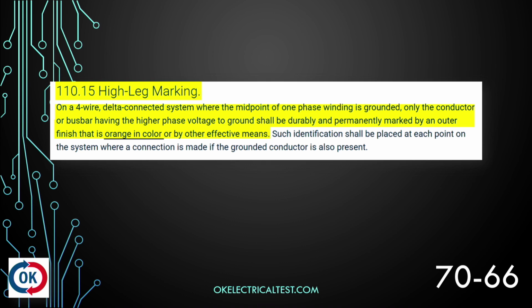110.15 high leg marking. It says on a 4-wire delta-connected system where the midpoint of one phase winding is grounded, only the conductor or bus bar having the higher phase voltage to ground shall be permanently and durably marked with an outer finish that's orange in color or by other effective means. So the high leg on a 4-wire delta-connected system can be marked, indicating with color the high leg, and that would be orange in color. All right, or it says we can also use other effective means. So that could be just a tag on there that just says high leg. That would be okay if I don't have orange on the truck.